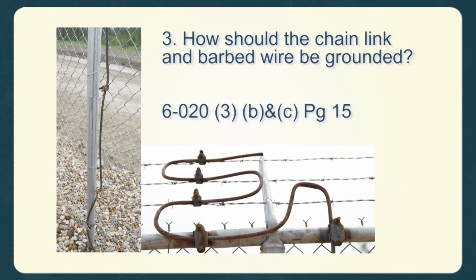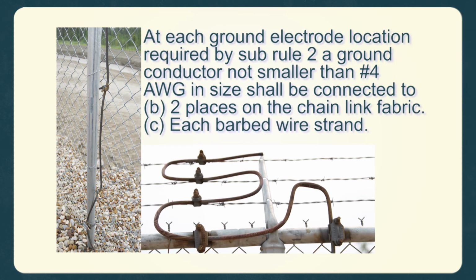Question number 3. How should the chain link and barbed wire be grounded? Answer: 6-020, number 3, B and C, page 15. At each ground electrode location required by sub-rule number 2, a ground conductor not smaller than the number 4 AWG in size shall be connected to B. 2 places on the chain link fabric, C. Each barbed wire strand.